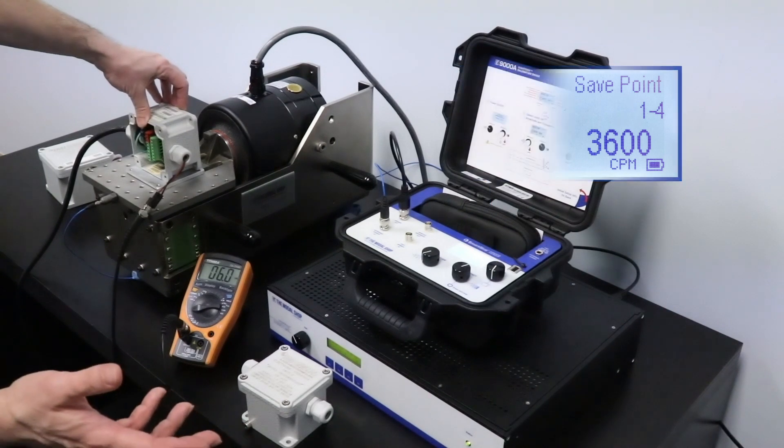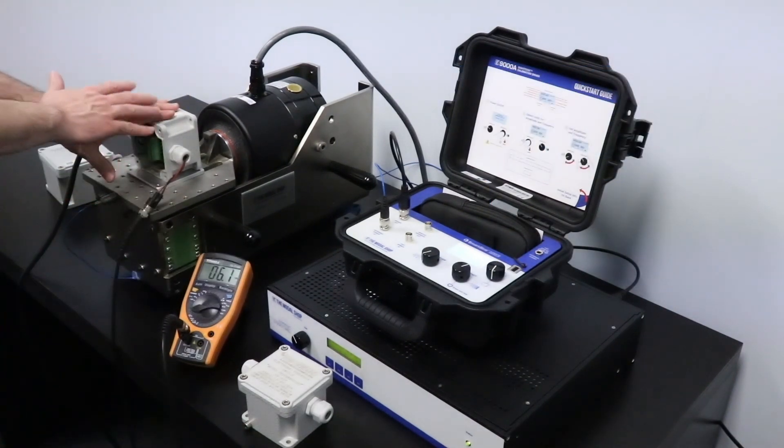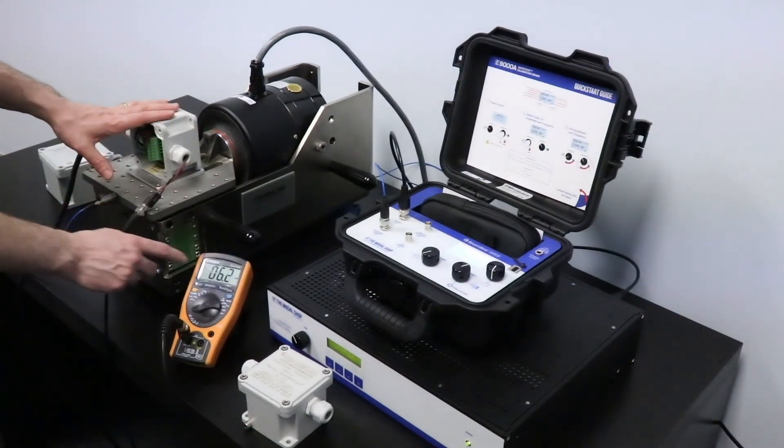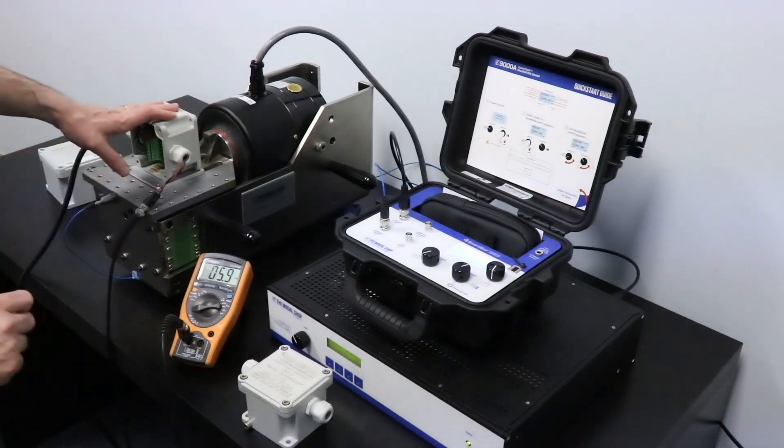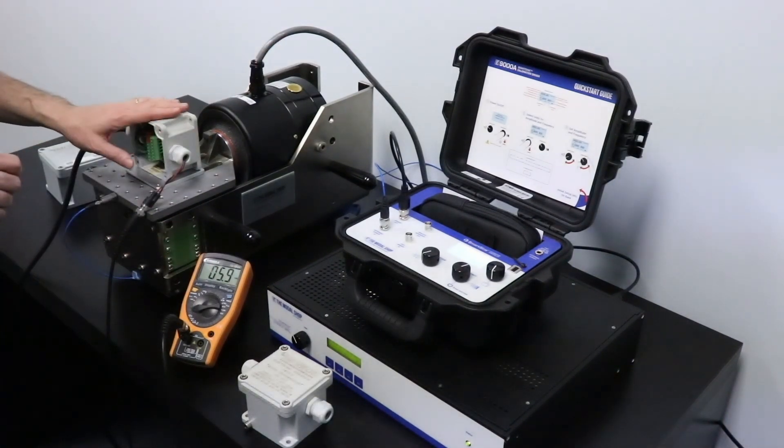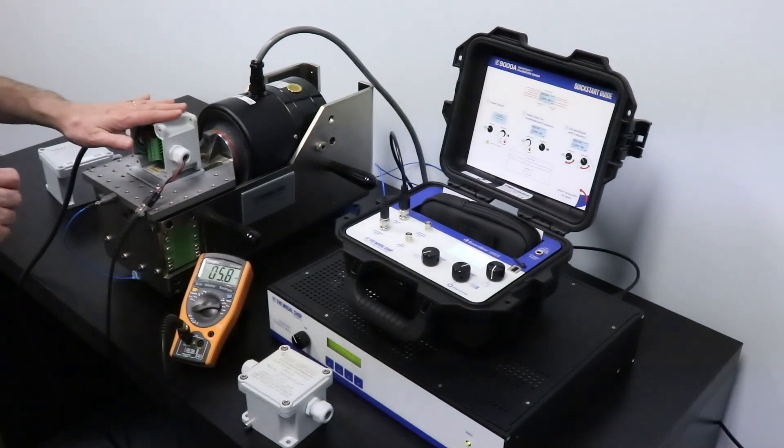So at this point, I can see my vibration switch is outputting a little bit of current. So that's a good indication. I'm sending the signal to my PLC and there's no tripping, no alarm, no alert.